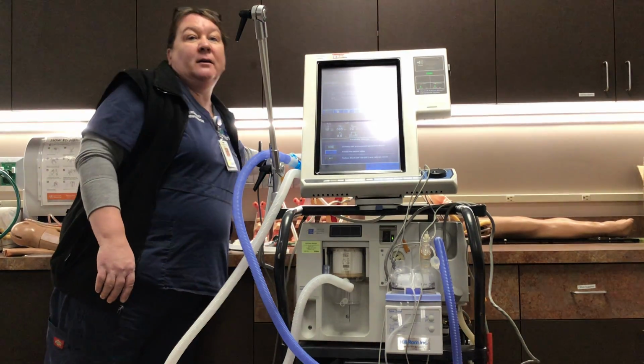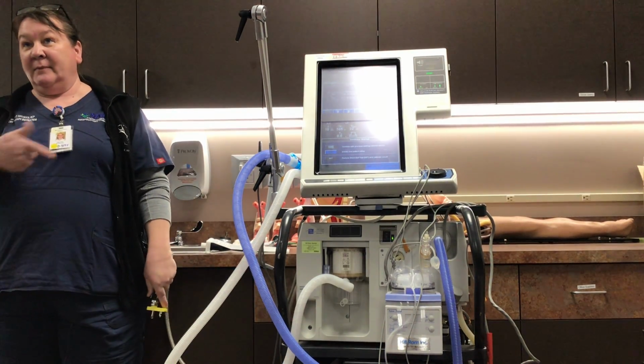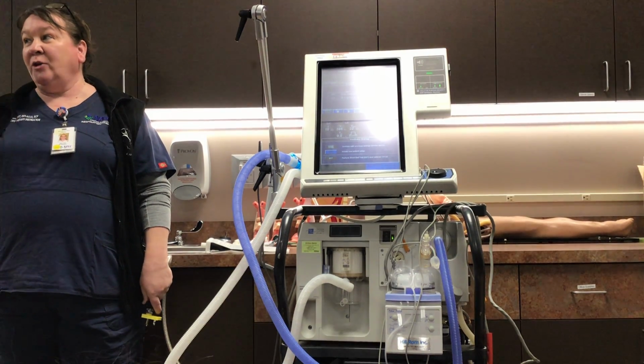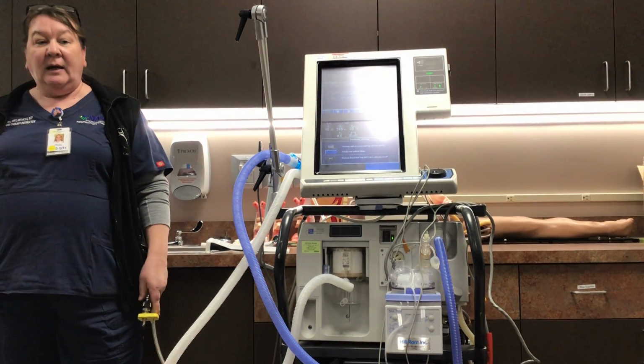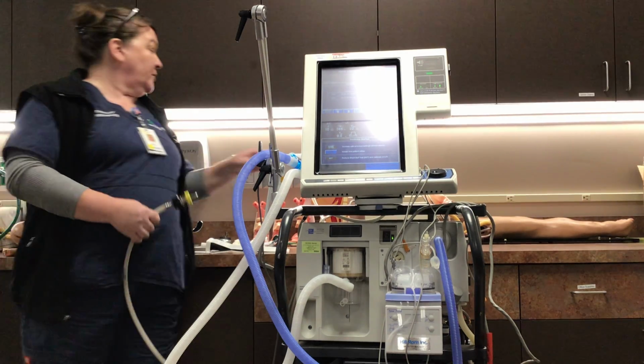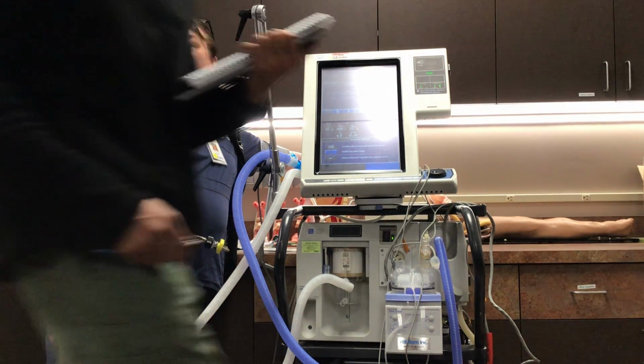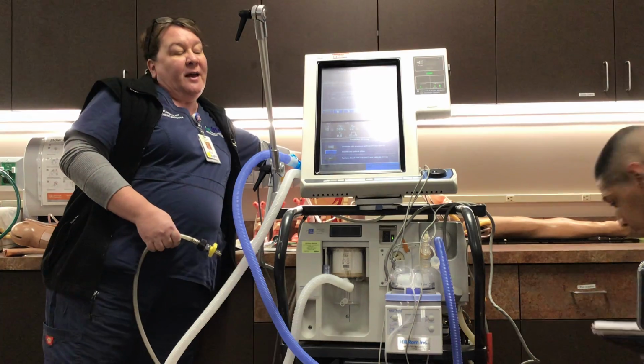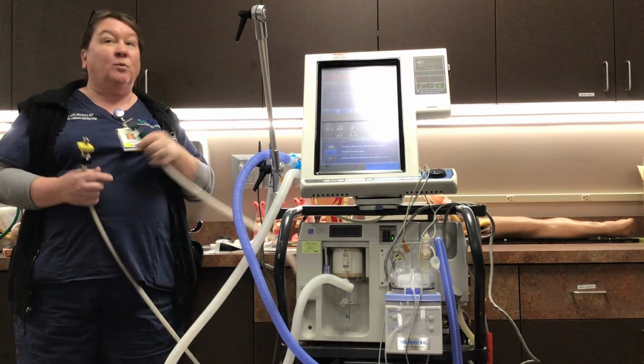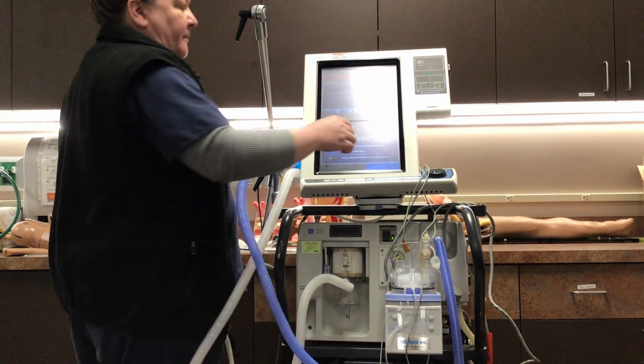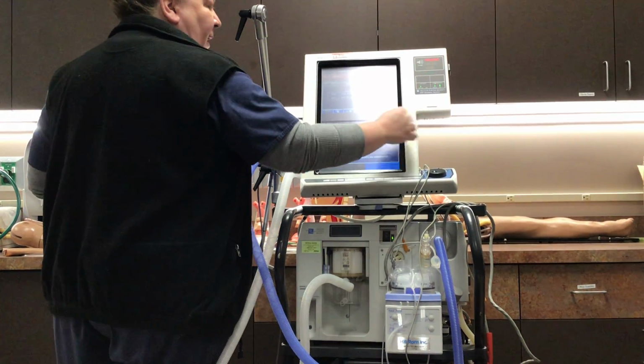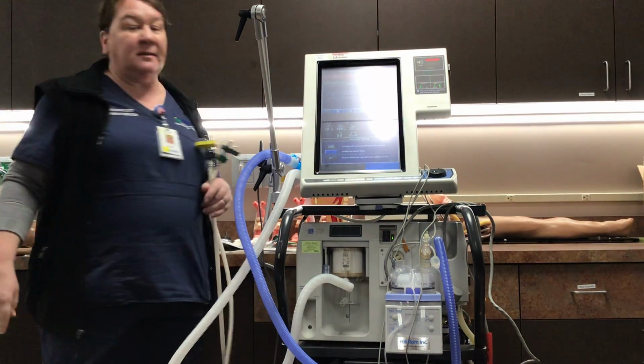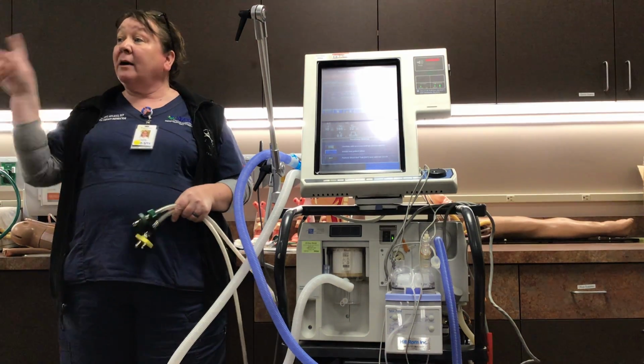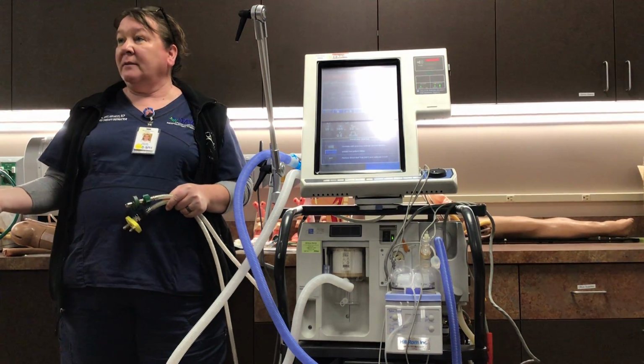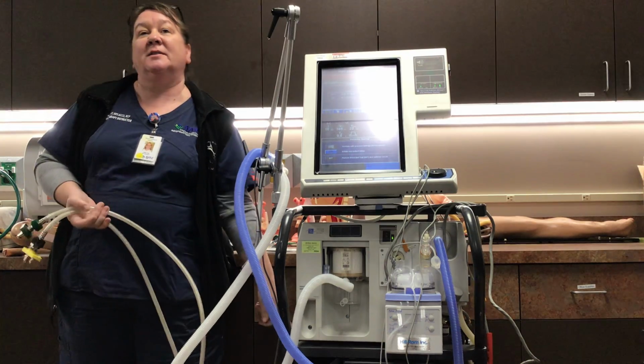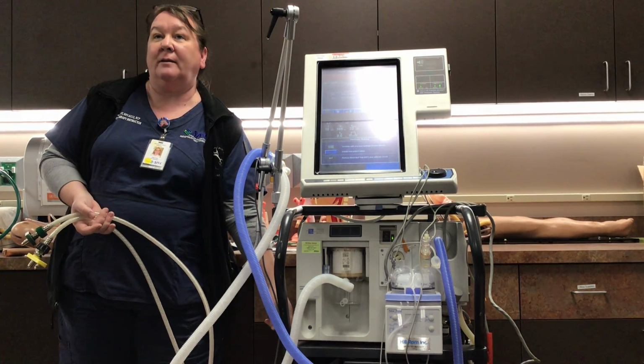But what happens if I lose my air? The air compressor is gonna kick in. So now you know it's running on the air compressor. And the other thing you'll see is because it has a built-in 50 PSI source, this vent will actually run without either one hooked up. It's gonna tell you there's no O2 supply, but I could run it down to room air, and it would run without alarming, because it doesn't need the O2 source, and it has its 50 PSI air source from within.